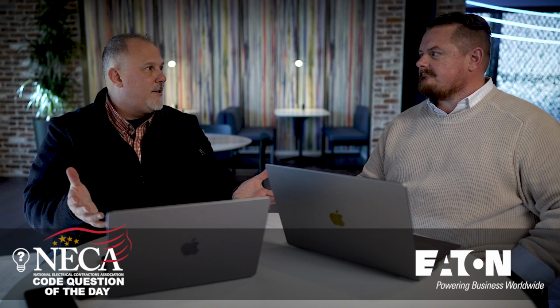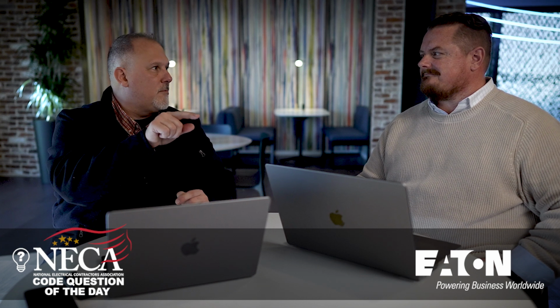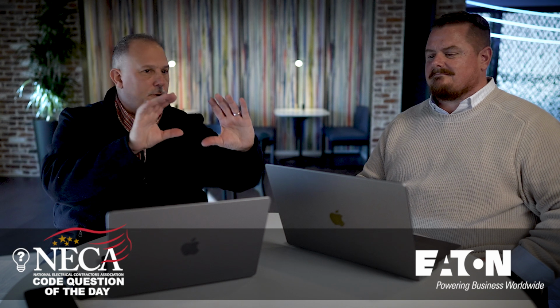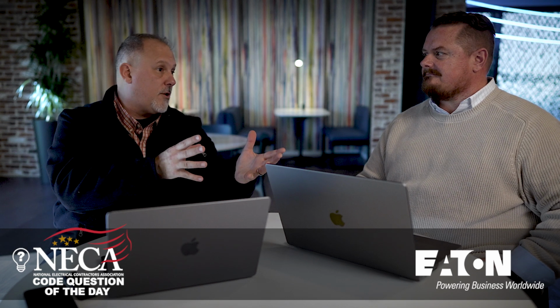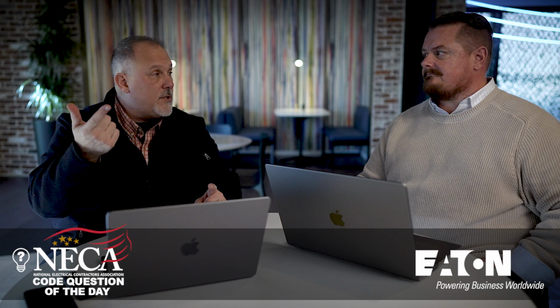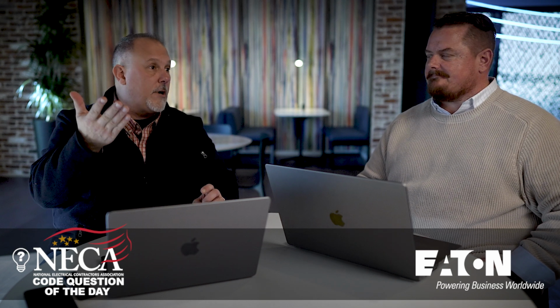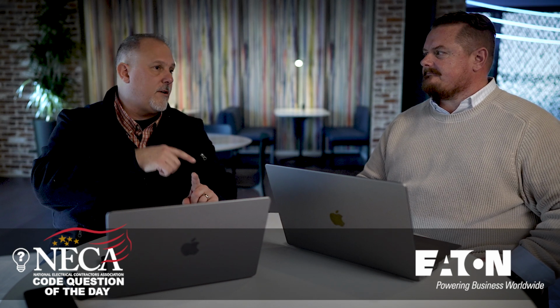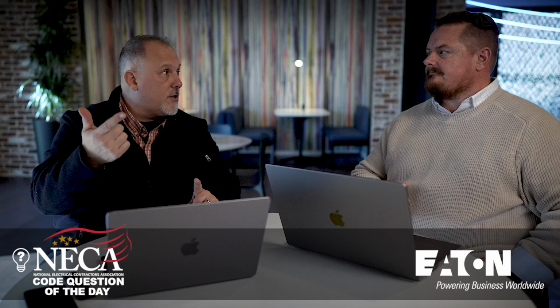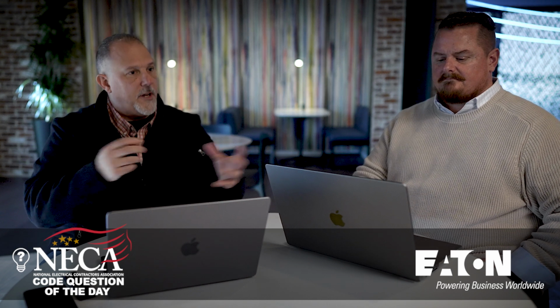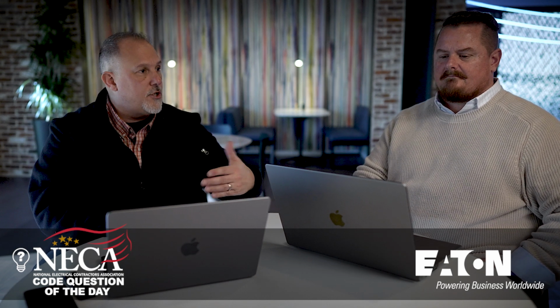You go, well, what is the power distribution block? What are all those different components? If there's a starter in there, do you have the right fuse ahead of it? If you put a breaker there, you can get it done with a breaker, but do you have the right circuit breaker? You've got to have the right combinations to make sure that you have the right short circuit current rating.